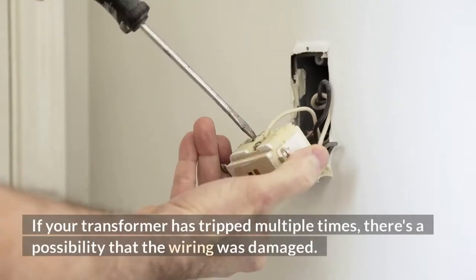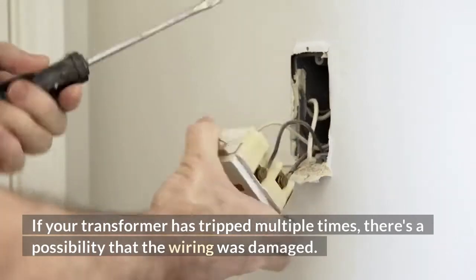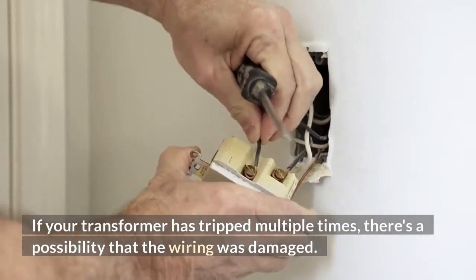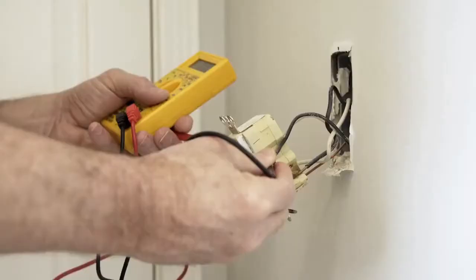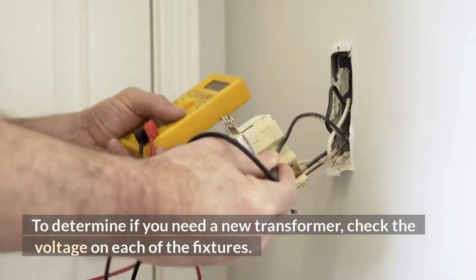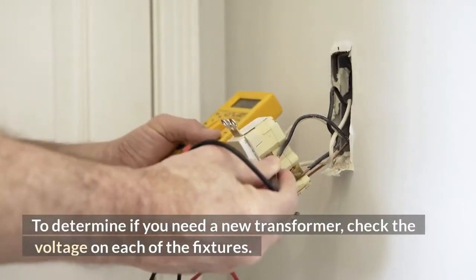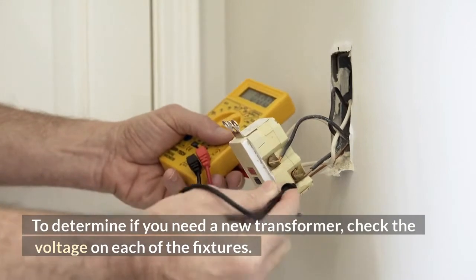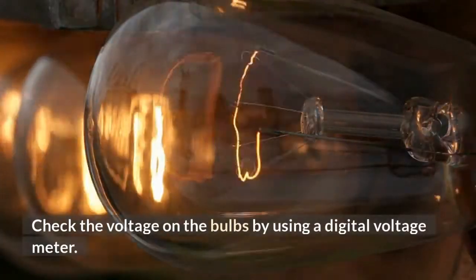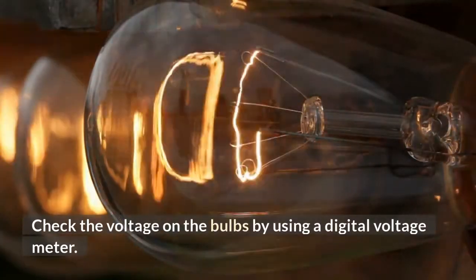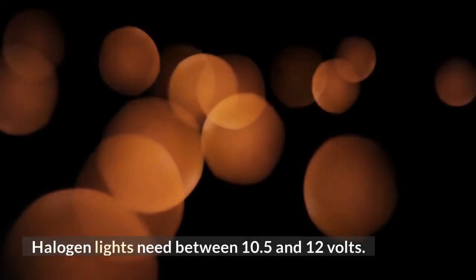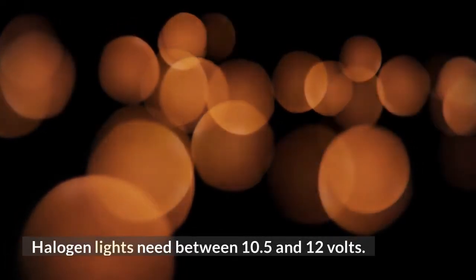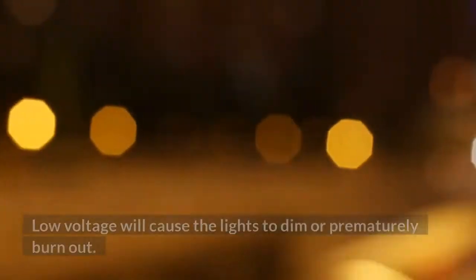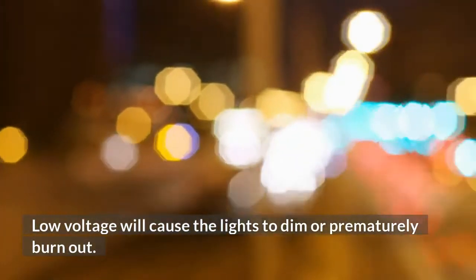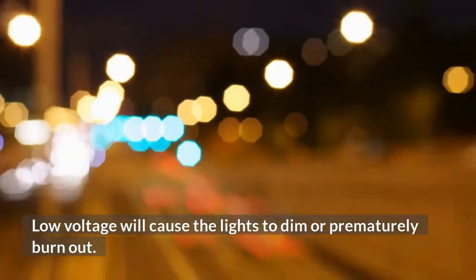If your transformer has tripped multiple times, there's a possibility that the wiring was damaged. To determine if you need a new transformer, check the voltage on each of the fixtures. Check the voltage on the bulbs by using a digital voltage meter. Halogen lights need between 10.5 and 12 volts. Low voltage will cause the lights to dim or prematurely burn out.